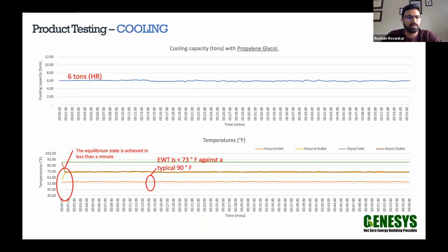The next couple of slides are our test data. We are using 30% propylene glycol on the closed loop side. This test data is for the device that you just saw in the last couple of slides. It is a 6-ton unit. In terms of capacity, it produces 6 tons pretty consistently. This test was done for about an hour, just to give you an idea of what the temperatures are.